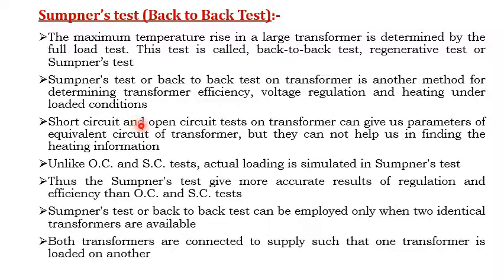There is one more test to determine the transformer efficiency and regulation, that is the open circuit and short circuit test. This open circuit and short circuit test gives the determination of the parameters of the equivalent circuit, but it cannot give the heating information. Thus, the Sumpner test gives more accurate results of regulation and efficiency than the OC and SC test.